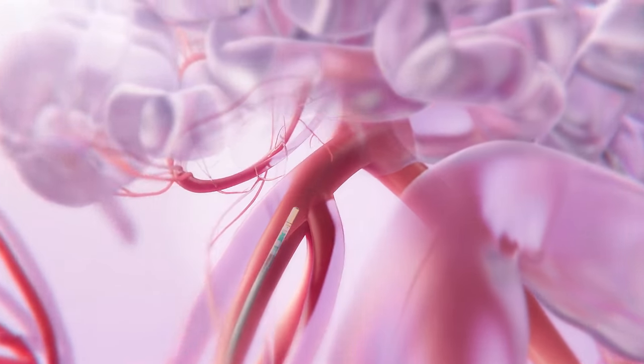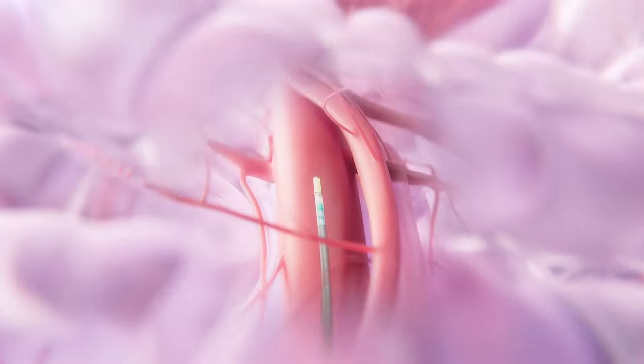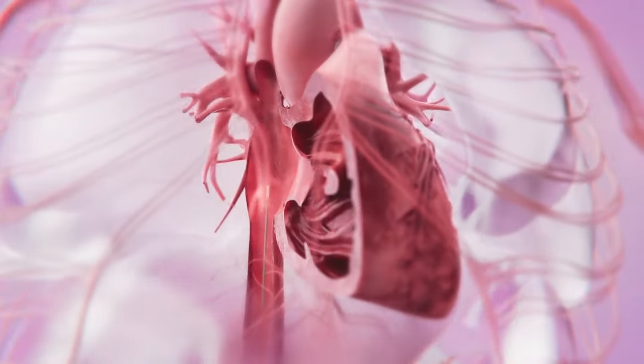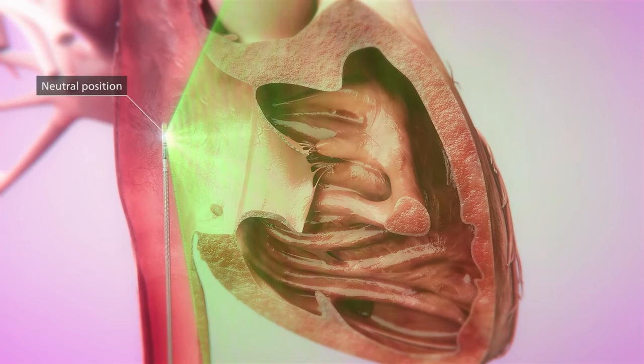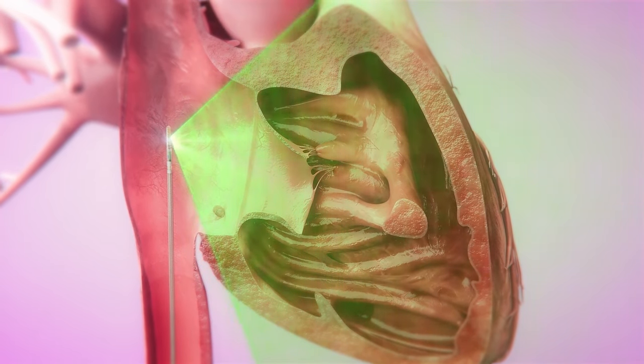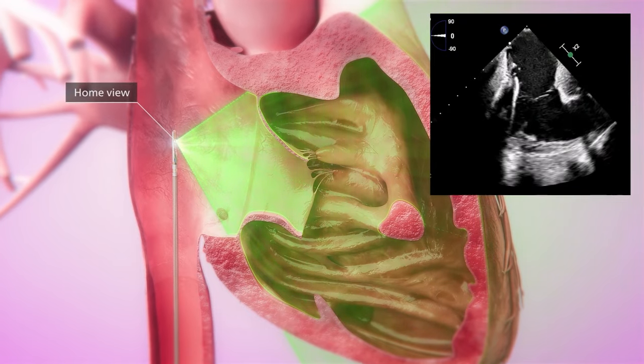When the Verisight Pro 3D ICE catheter enters the body with the clutch knob facing the ceiling, the imaging sector will be in neutral position. A slight clockwise adjustment will visualize the home view.